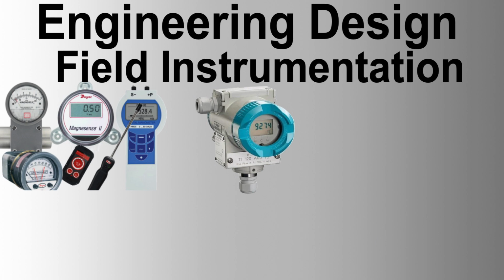Site acceptance test. A site acceptance test must be performed on all instruments after installation to verify their performance and compliance with the specified requirements. The SAT must include functional testing, calibration, and any other tests necessary to confirm that the instruments meet the performance standards specified in the datasheets and specifications. SAT reports must be provided to the purchaser for review and approval.